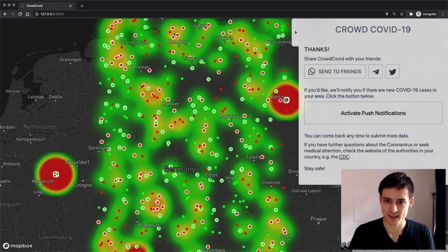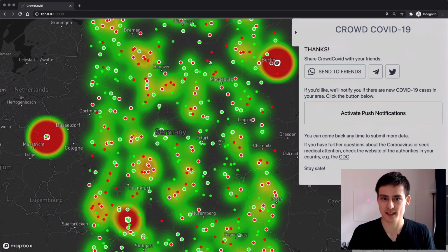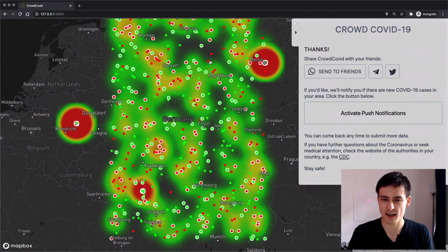All right, so finally, maybe a final thing is, why is this a medical device? I have to confess, I don't think this would actually be a medical device per the MDD or MDR definition, because we're literally just tracking statistical data on COVID symptom occurrences across the world on a map. If you go back to the MDD and MDR definitions of a medical device, you will notice we probably don't fulfill any of that.